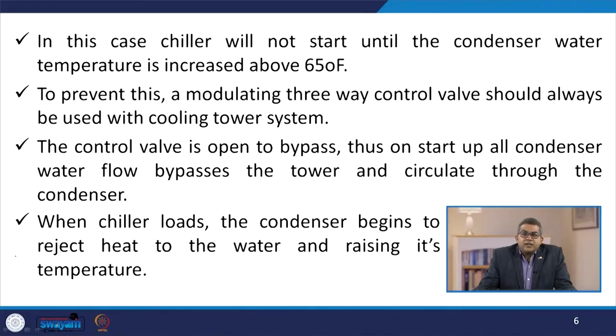The chiller will not start until the condenser water temperature is increased above 65 degrees Fahrenheit. To prevent this, a modulating three-way control valve should always be used with a cooling tower system. The control valve is open to bypass, so on startup all condenser water flow bypasses the tower and circulates through the condenser. When the chiller loads, the condenser begins to reject heat to the water, raising its temperature.